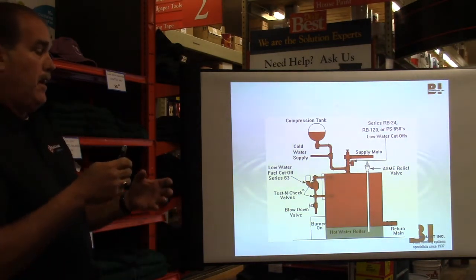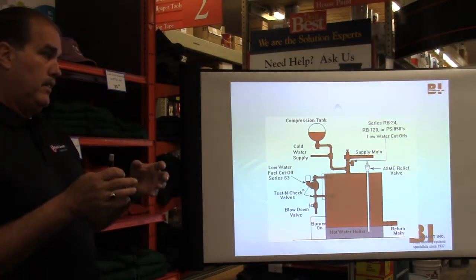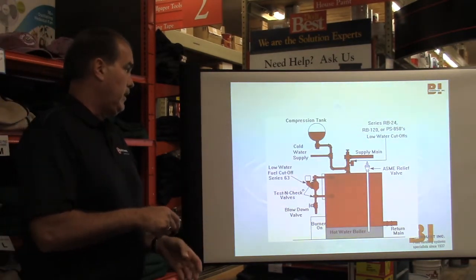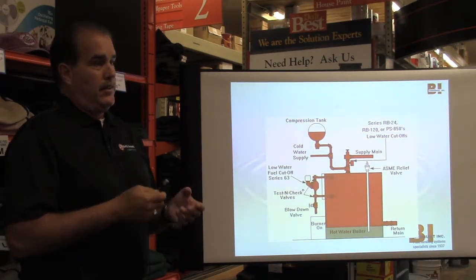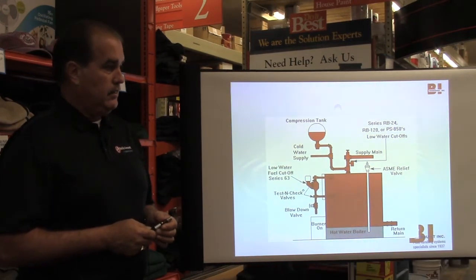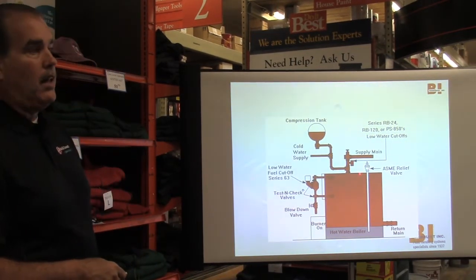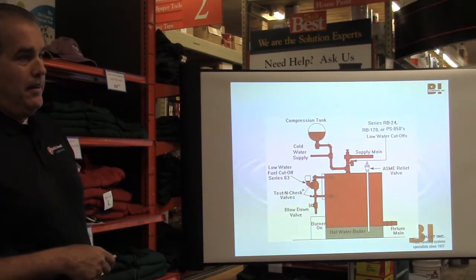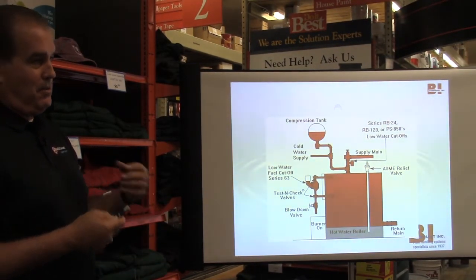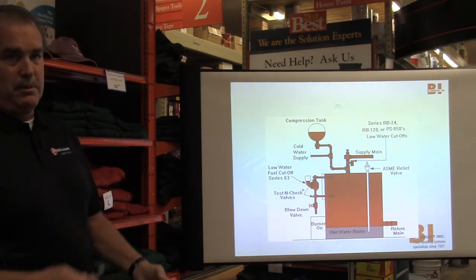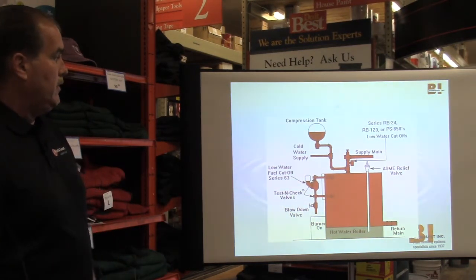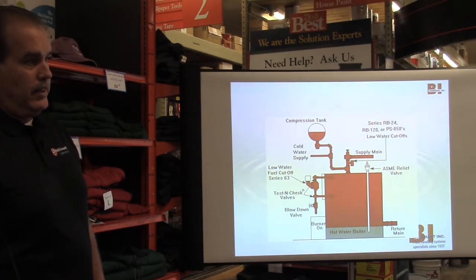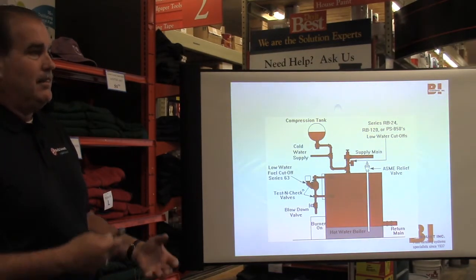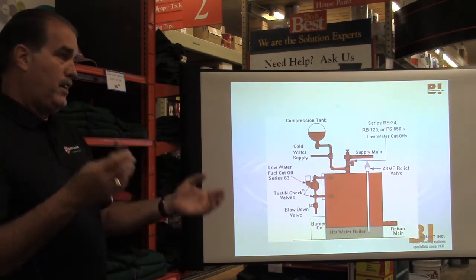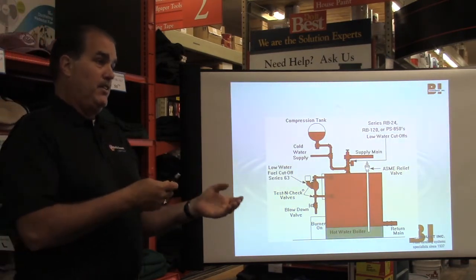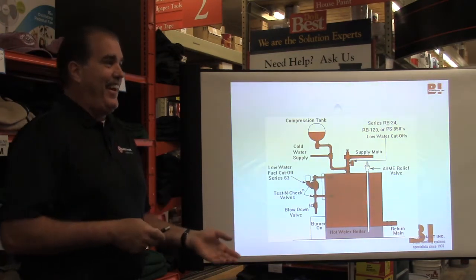Now, on the maintenance side, if you read the manufacturer's manual, which you probably won't have, they're going to say you should open that up once a year to test it, because they want to make sure it's not clogged or plugged up. The problem is sometimes when you open it up and go to shut it, it doesn't shut off tight because debris gets caught between the seat, and now you've got a leaking valve that wasn't leaking before. The manufacturer has to say yes. I'm just letting you know you might have to buy a new valve afterwards.